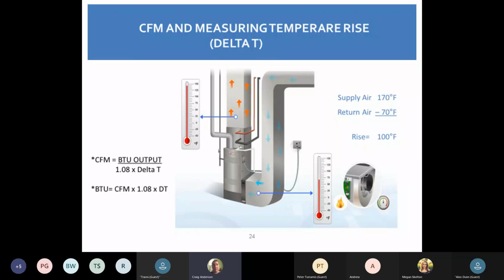So if we're doing a temperature rise on the furnace in heating mode, we're checking the supply and return temperature at the same time. It's a lot easier. Two pocket thermometers, one in the supply, one in the return. Start your furnace, let it run for 10-15 minutes, get it running, make sure your temperature rises in the parameters of what is set on the furnace.